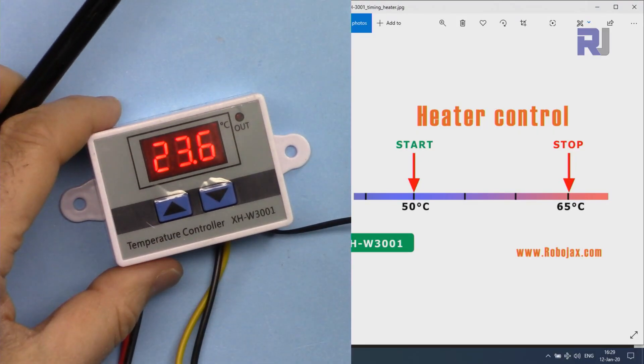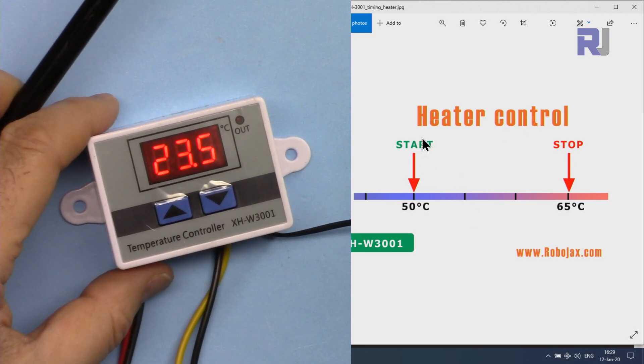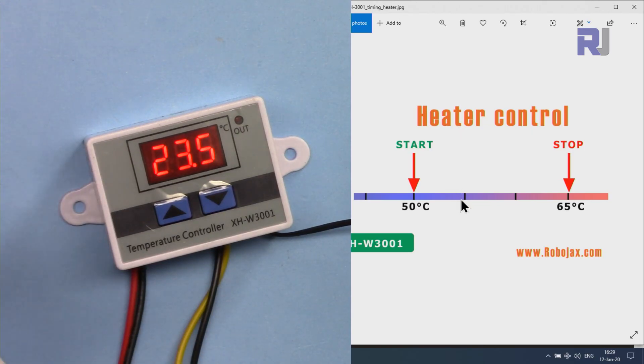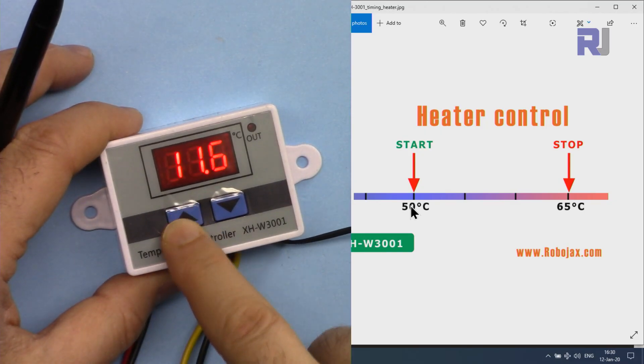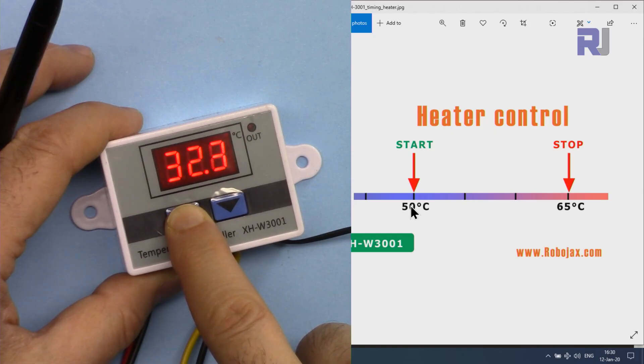We have a start temperature of 50 degrees and stop temperature of 65 degrees. And how it works is that because this is a heater, we are keeping the heat. Meaning if the temperature goes below 50 it will start and will heat up, and we don't want above 65 or whatever temperature you want - so that's our stop temperature. Now let me set the start for 50. So if I press this, that's the start, and then hold it again.